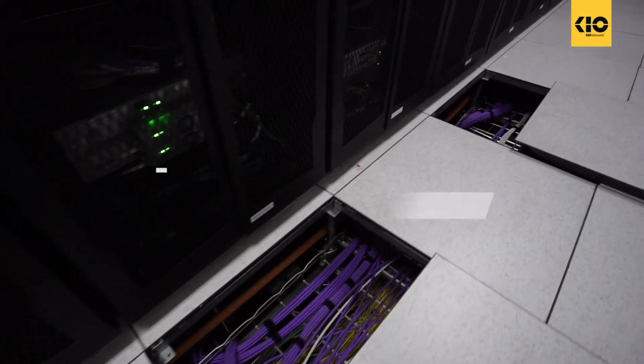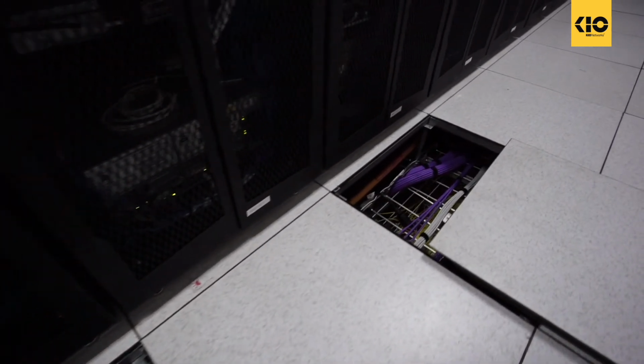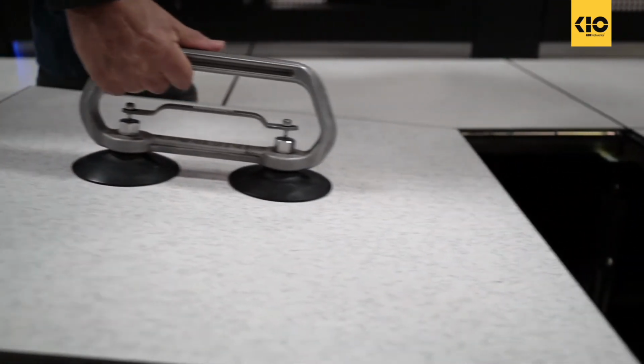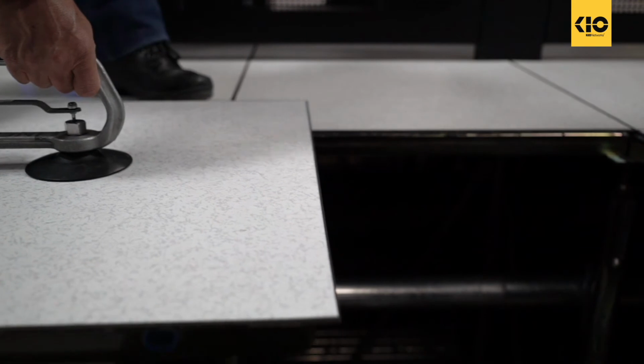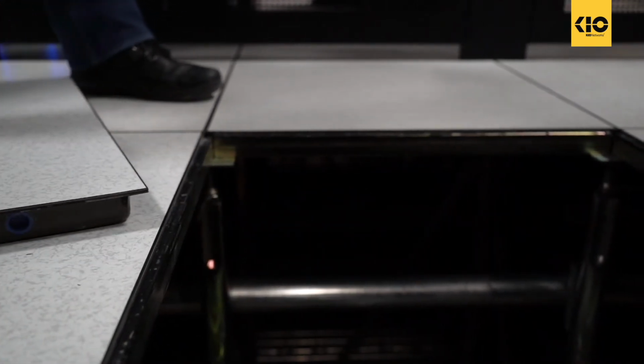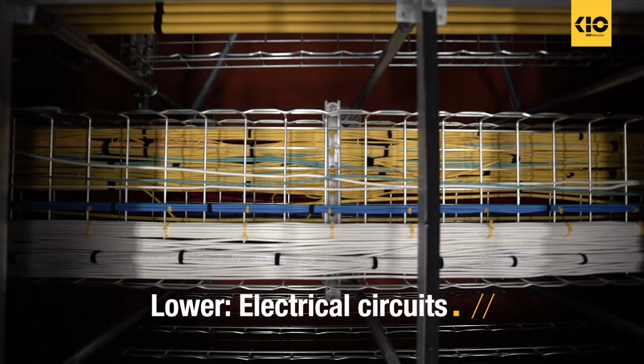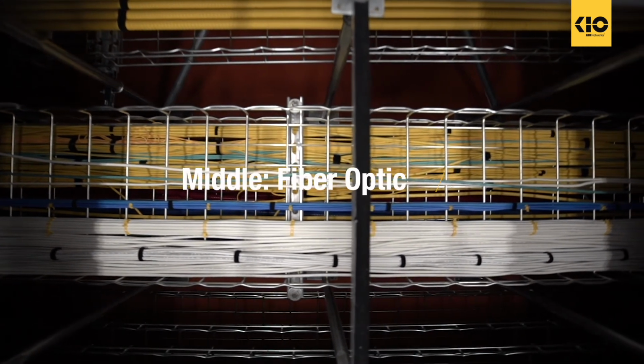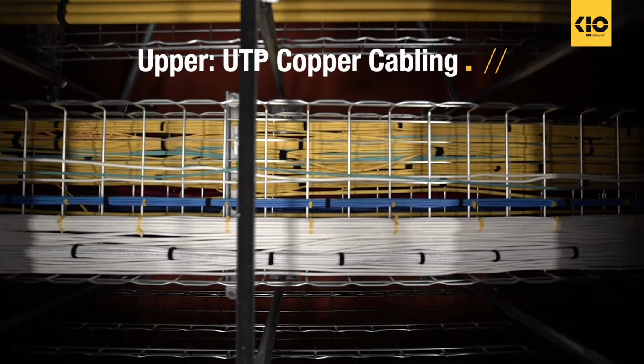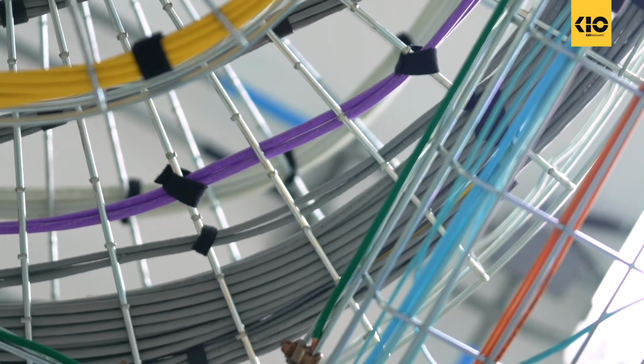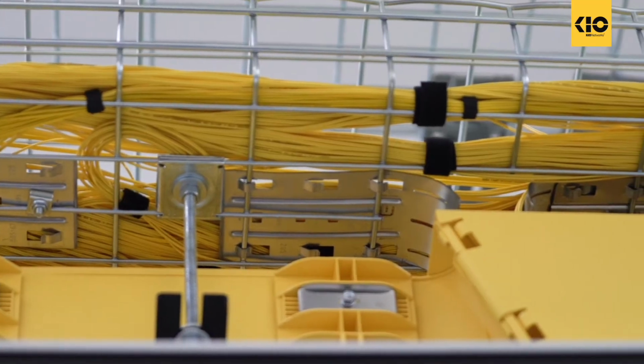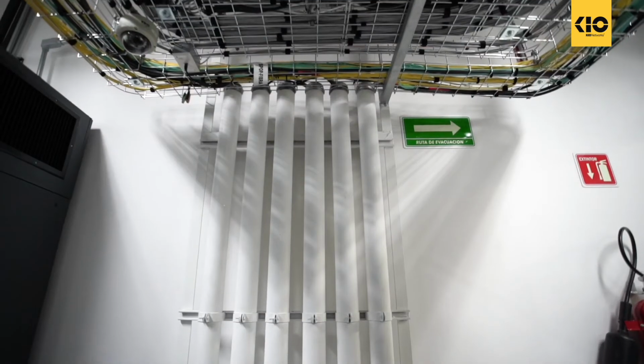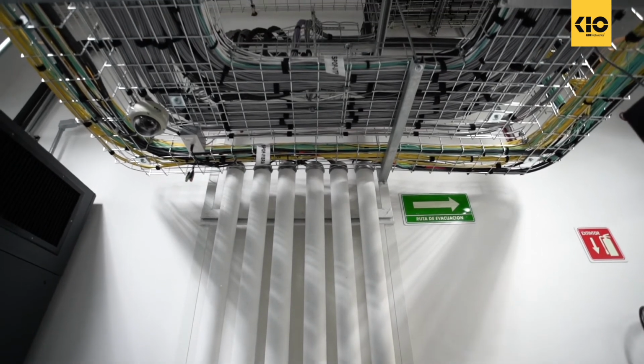The elevation of the full plenum reaches 90 cm, which allows a perfect distribution of the air in it. Besides, the cable distribution trays do not impede airflow. It is essential to mention that this height allows us to handle the 3 levels of trays. In the lower one, we have the electrical circuits. In the middle, we lay the fiber optic. And in the upper one, we have the UTP copper cabling. With this, we mitigate any interference by the electromagnetic fields of the circuits, and at the same time, we allow the adequate flow of cold air.